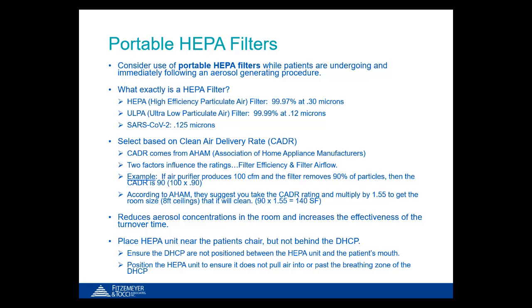There is one step above a HEPA filter, called a ULPA, or ultra low particulate air filter, which captures 99.99% of particles at 0.12 microns or larger, smaller than the coronavirus, so in its finest form it will catch everything. The problem with the ULPA filter is it's very restrictive and can really reduce the amount of air delivery to the space, so you have to consider the options when selecting this equipment.